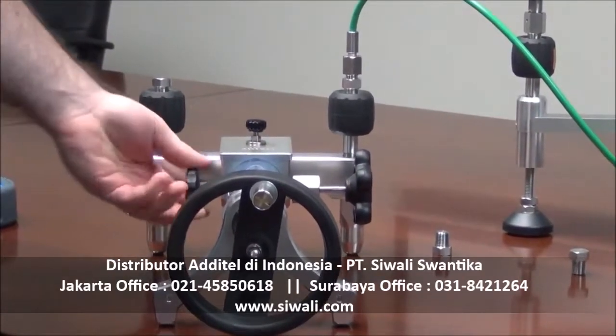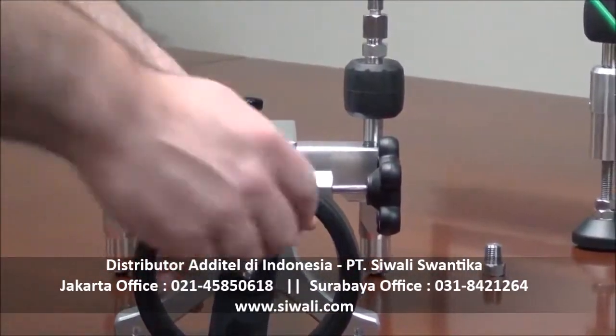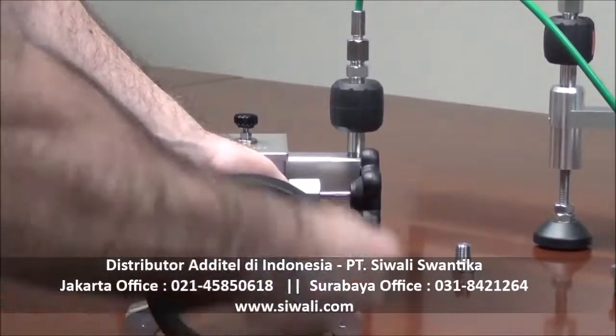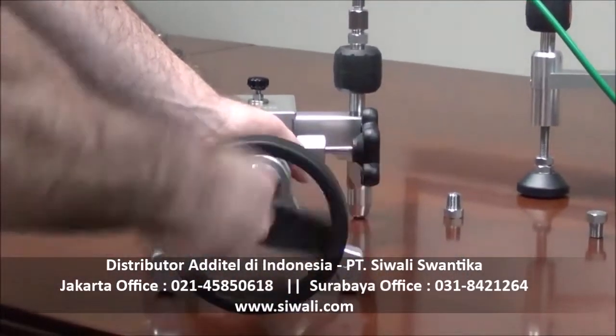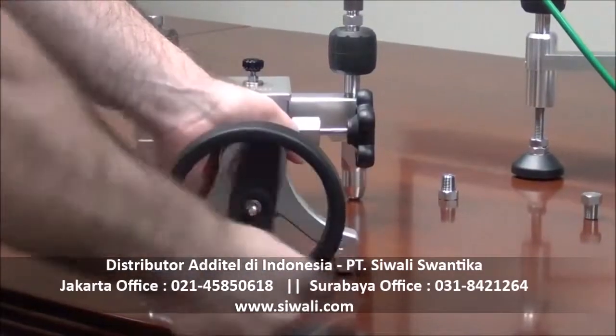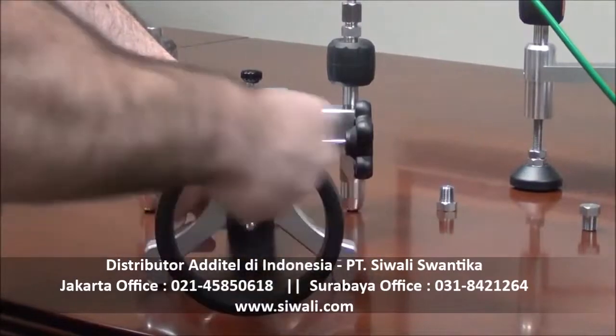First thing I'm going to do is go ahead and pull a vacuum on it. This is the vacuum valve here, the vent valve here — I'm going to close that. And then I'm going to go ahead and bring it all the way out. I just set this up so I'm sure there's gas in the system that we need to get out.